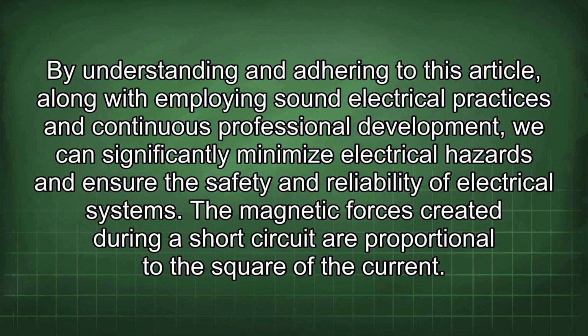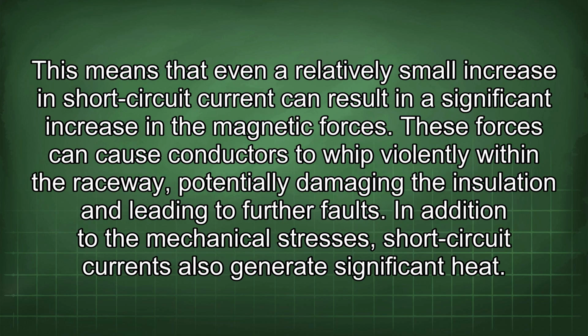The magnetic forces created during a short circuit are proportional to the square of the current. This means that even a relatively small increase in short circuit current can result in a significant increase in the magnetic forces. These forces can cause conductors to whip violently within the raceway, potentially damaging the insulation and leading to further faults. In addition to the mechanical stresses, short circuit currents also generate significant heat.